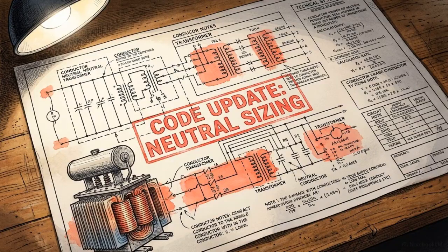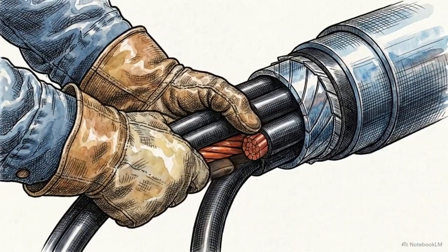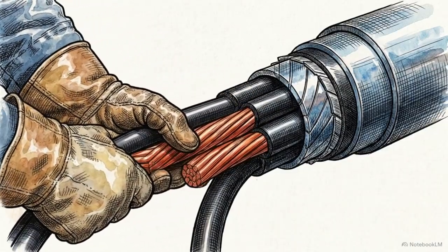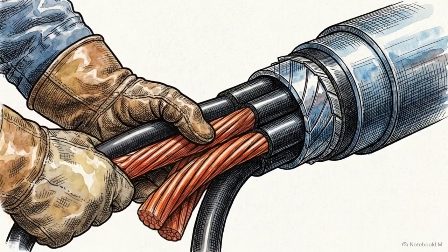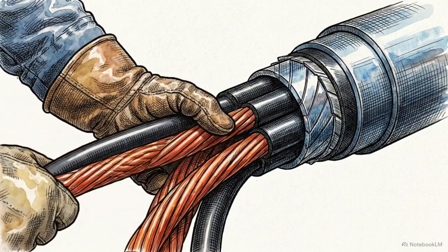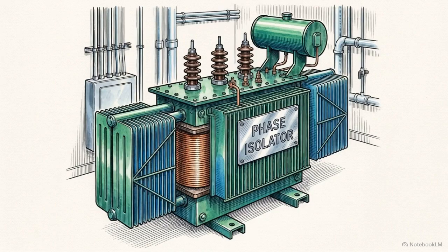To stop these fires, modern electrical codes now mandate brute force solutions. Electricians are required to pull double-sized neutral cables or run completely separate neutral wires for every single phase. But there is also a more elegant defense deployed at the hardware level: isolation transformers, designed specifically for harmonic mitigation.